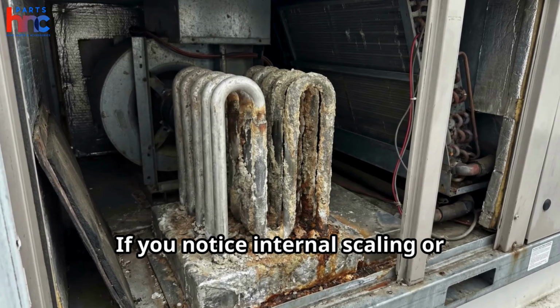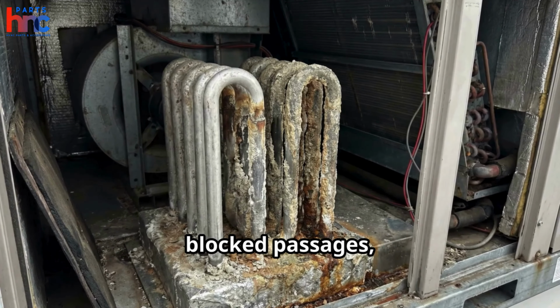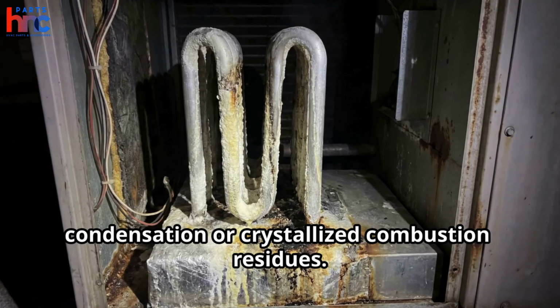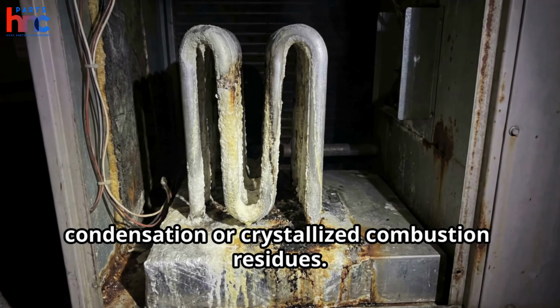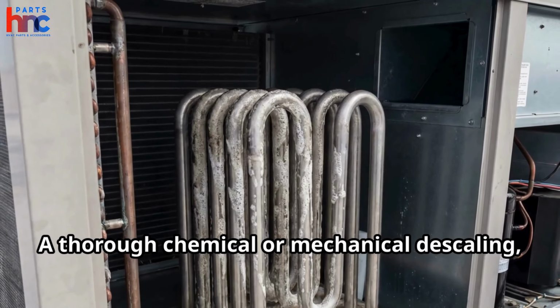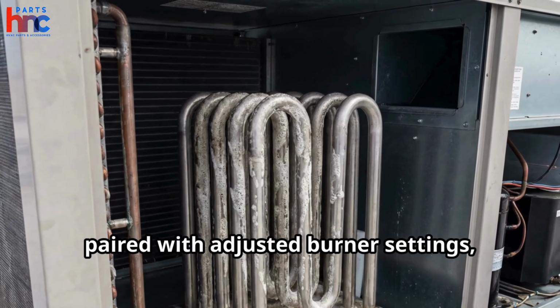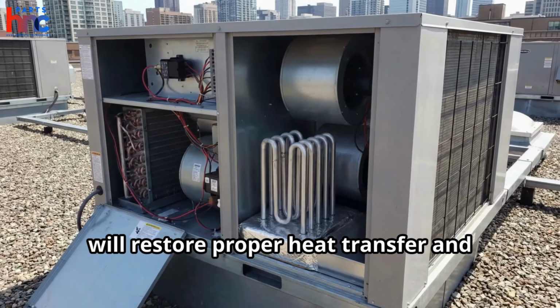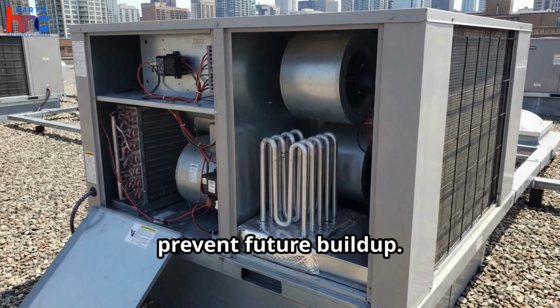If you notice internal scaling or blocked passages, this is usually due to hard water condensation or crystallized combustion residues. A thorough chemical or mechanical descaling, paired with adjusted burner settings, will restore proper heat transfer and prevent future buildup.